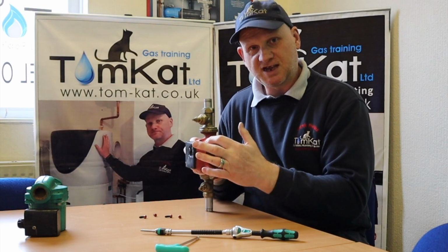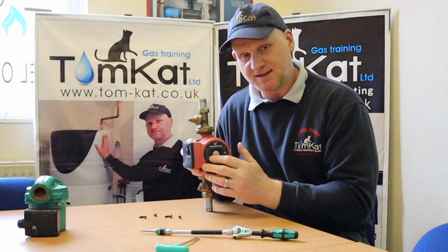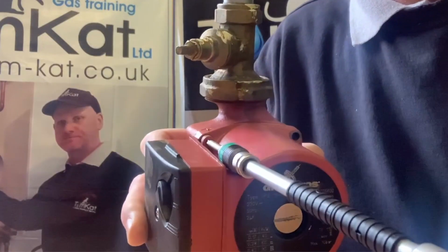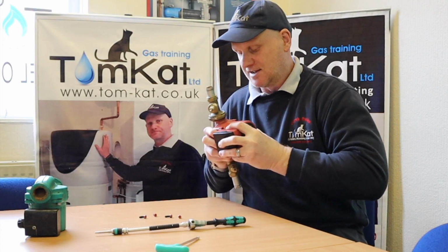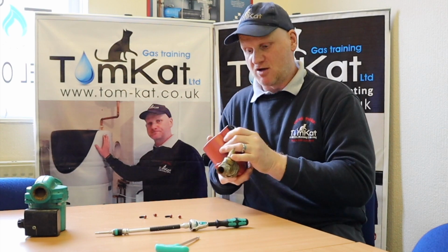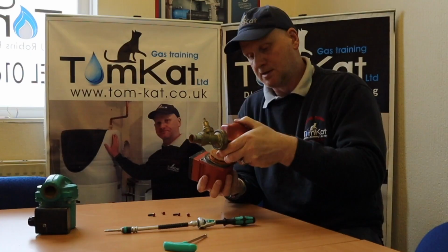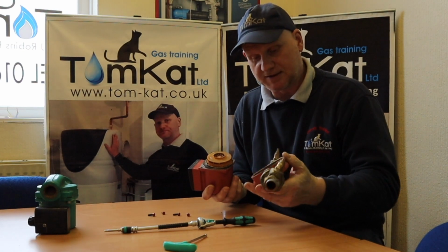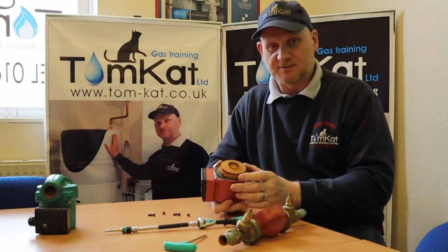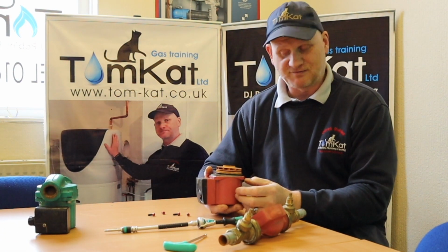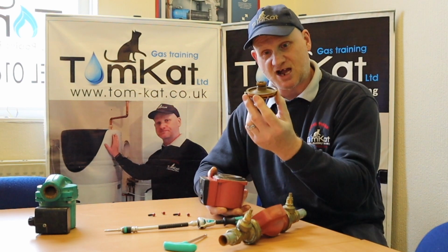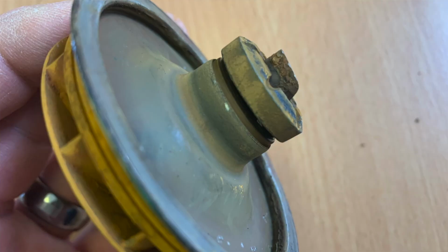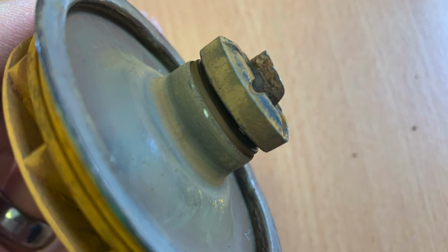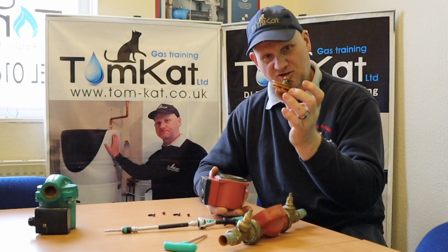First of all, you can see the pump head is designed so you can actually get in to undo the Allen screws. So that's the first thing. Now, I don't think this one has ever been off. So now we've pulled this apart, I can see the reason why this is in the centre, because the first thing I notice is the shaft. The impeller has snapped off the ceramic shaft. So that's the first thing what's wrong with this.